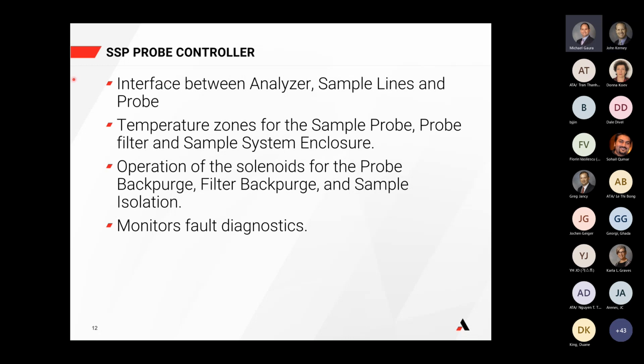Okay. In addition to the controlling of the temperature zones, which, hopefully it was very clear from Rod's walkthrough, is of critical importance is maintaining temperatures above the dew point. We also need a way to drive some of those solenoids that do the back purges for both the filter as well as the probe. We need to isolate the sample while we're doing those back purges, because we don't want to be shoving instrument air into the analyzer path during that blowback. We want it all concentrated on the filter that's up in the probe enclosure as well as the probe tube.